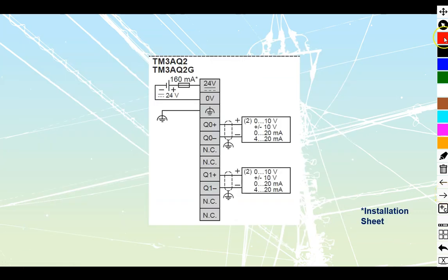Looking at the wiring for these cards, we see that we need an external power supply. So this 24 volt power supply is going to run through a fuse. We're going to run the negative in as well and ground the card. This provides the power that my controller is then going to provide a signal out with. It's going to convert that, chop it down, and we're going to get our 0 to 10 volt or plus or minus 10 volts out of it.